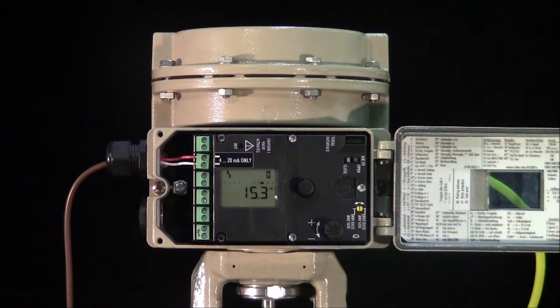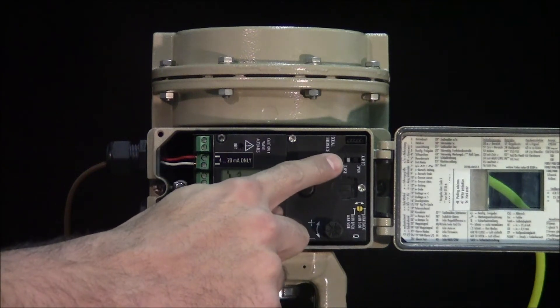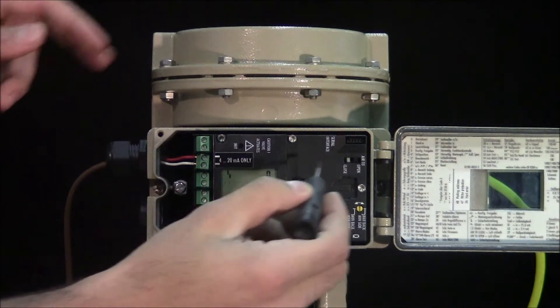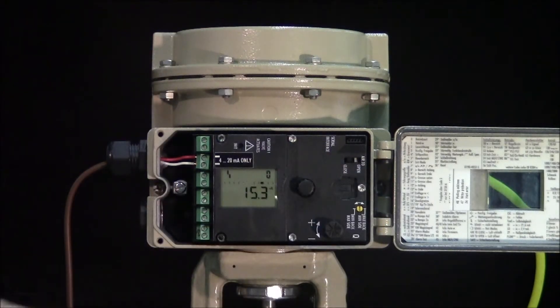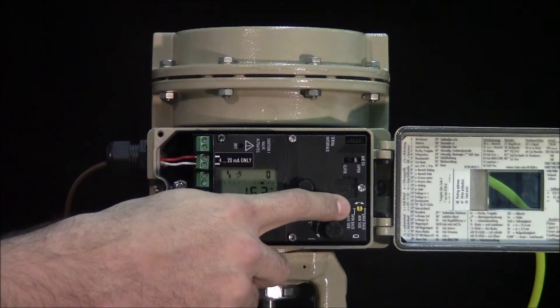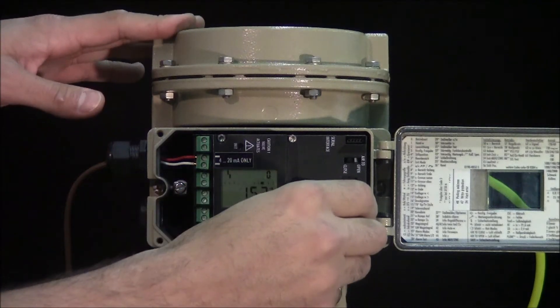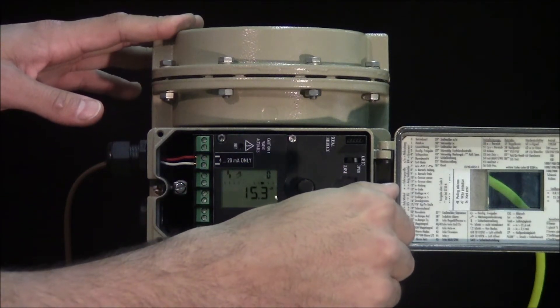This actuator fails open upon loss of air supply, therefore our first step will be to set our positioner for the air-to-close operation. For the 120 actuator, it's advisable to restrict the flow. This will prevent overshooting of our set point.